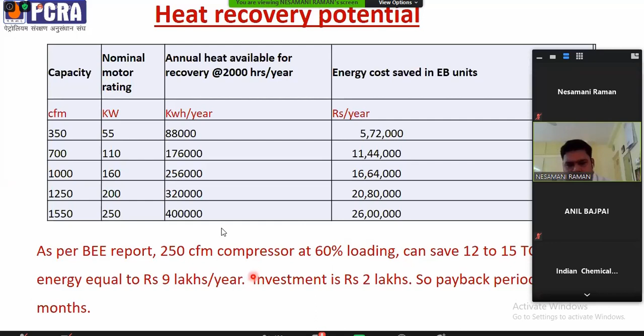a 250 CFM compressor at 60% loading, because no compressor will always be at 100% load. Load will be varying continuously, so for an optimum case we have taken 60% loading. It can save almost 12 to 15 tons of oil equivalent of energy per year, which is equal to almost 9 lakhs per annum. The investment cost of a heat recovery system in a compressor is 2 lakhs. So the payback period is around 4 months. This is one case study to support the technology.